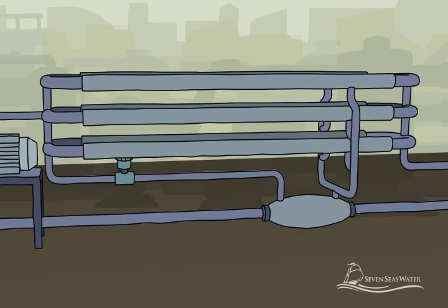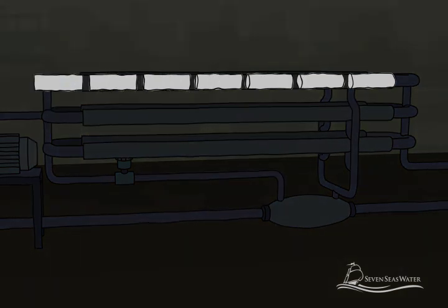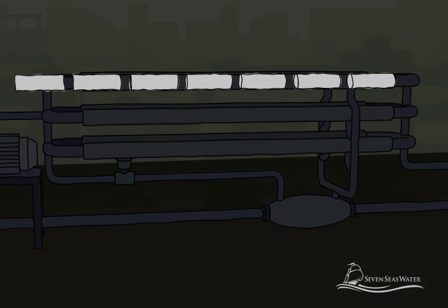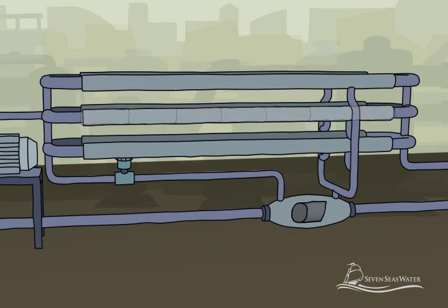The reverse osmosis membranes are then enclosed in a fiberglass shell. The membranes are connected end-to-end, usually six to seven membranes together, and housed in vessels that are built to withstand pressures up to 1,200 psi.